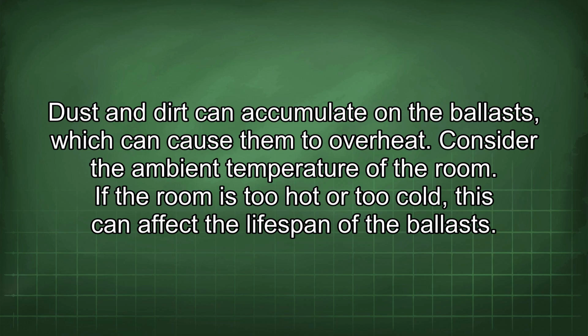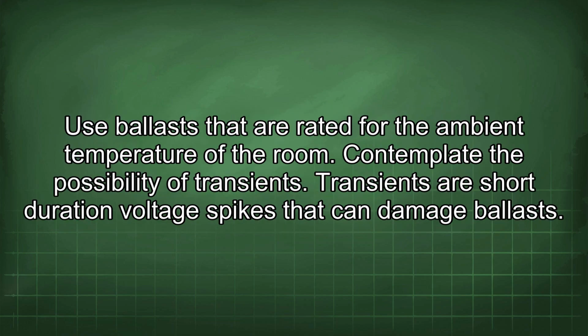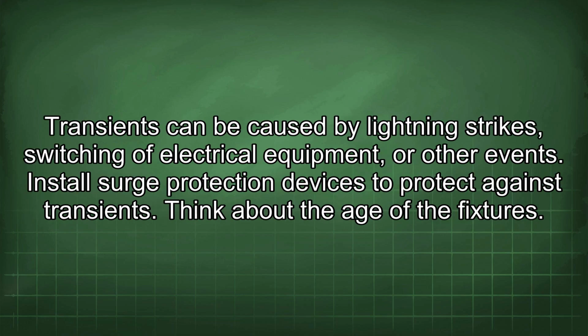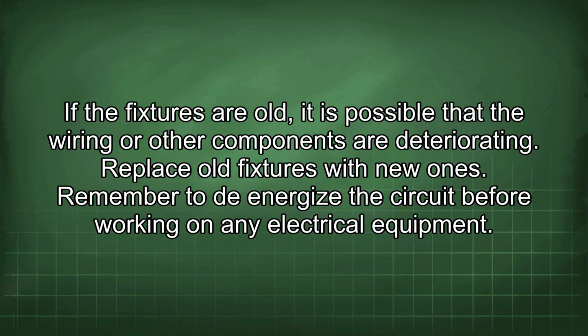Consider the ambient temperature of the room. If the room is too hot or too cold, this can affect the lifespan of the ballasts. Use ballasts that are rated for the ambient temperature of the room. Contemplate the possibility of transients. Transients are short-duration voltage spikes that can damage ballasts. Transients can be caused by lightning strikes, switching of electrical equipment, or other events. Install surge protection devices to protect against transients. Think about the age of the fixtures. If the fixtures are old, it is possible that the wiring or other components are deteriorating. Replace old fixtures with new ones.